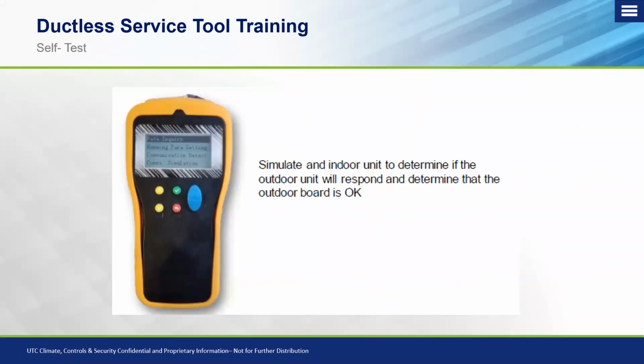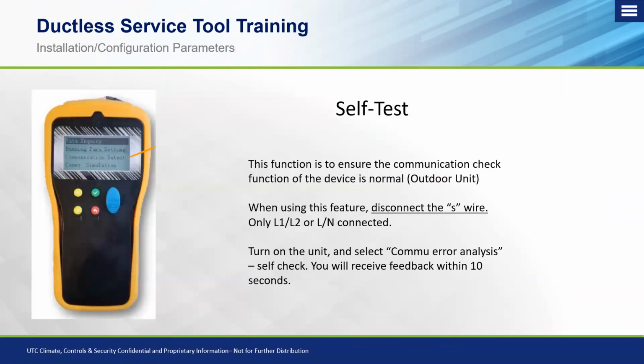Okay, so getting into the self-testing menu. The self-testing menu is to simulate an indoor unit to determine if that outdoor unit will respond and determine, more importantly, that the outdoor unit board is working properly. So we want to make sure that the outdoor unit is responding properly. We're going to use this tool to act as a fake indoor unit to send a control signal to it and make sure we get a proper response back.